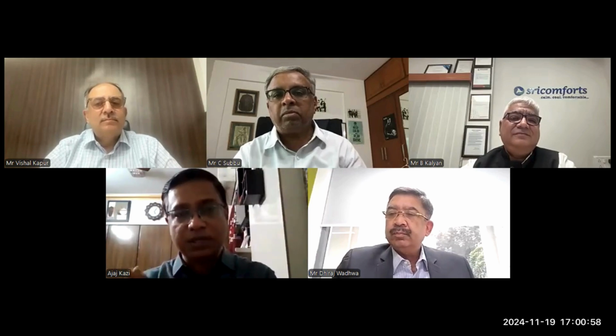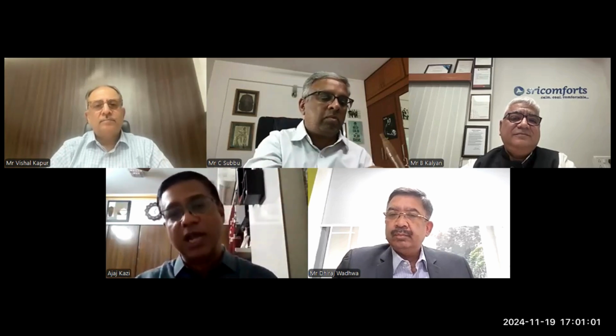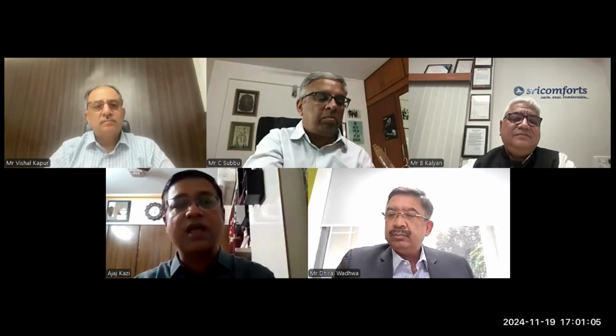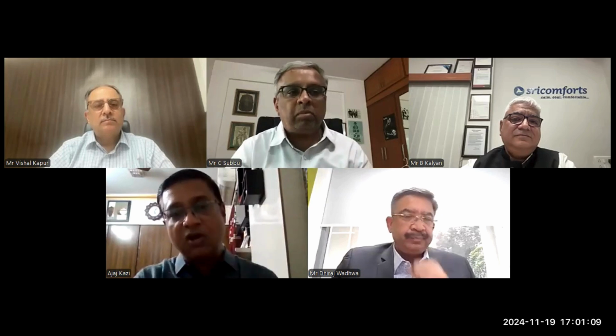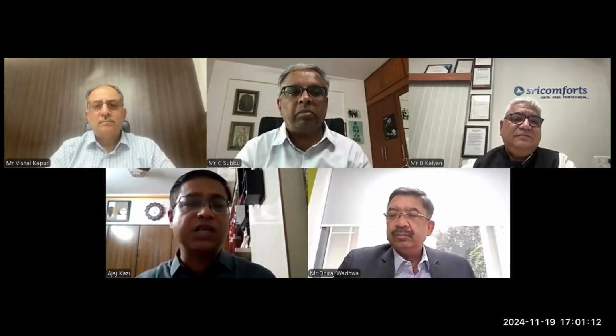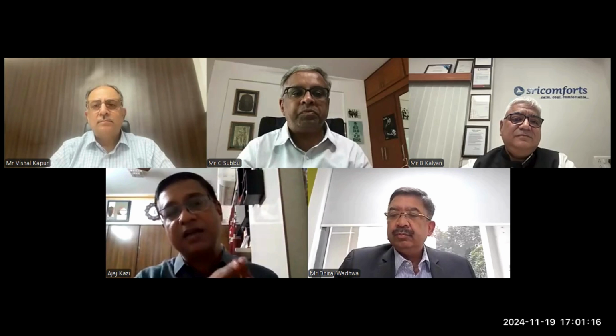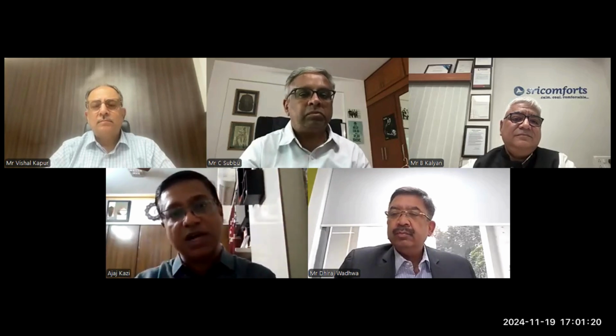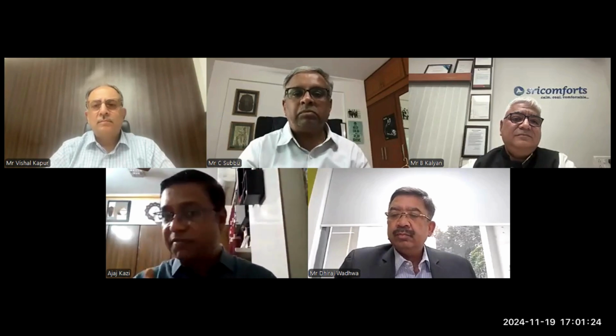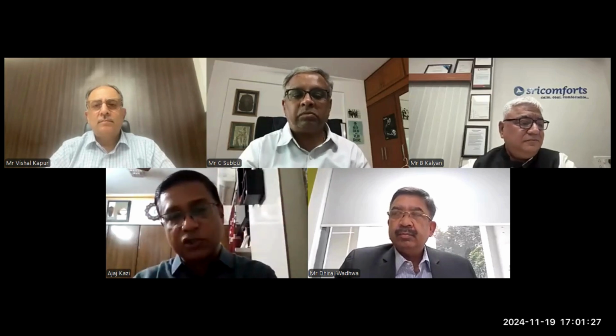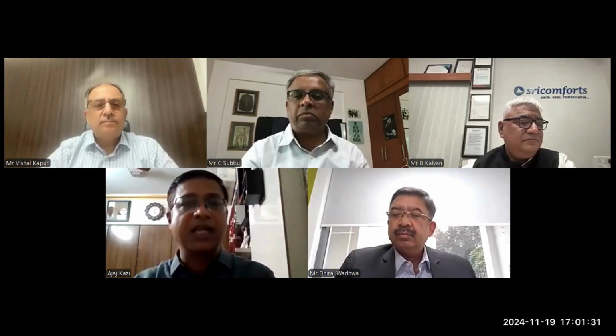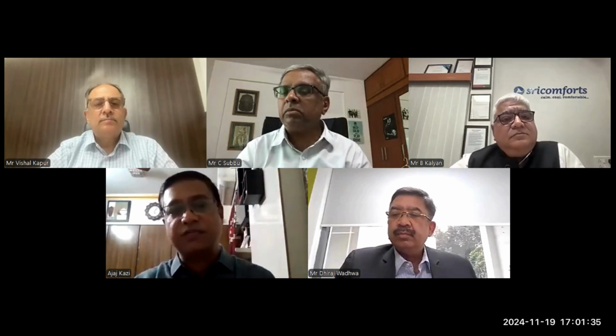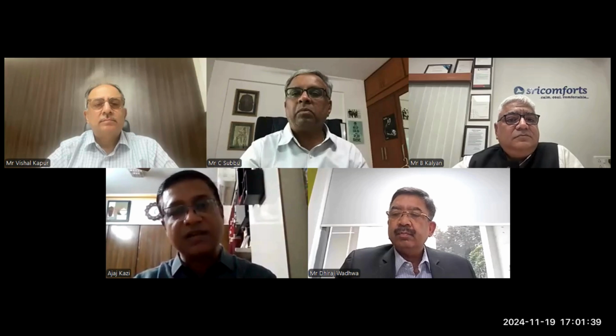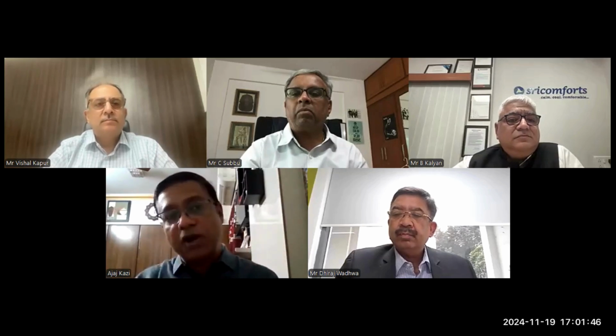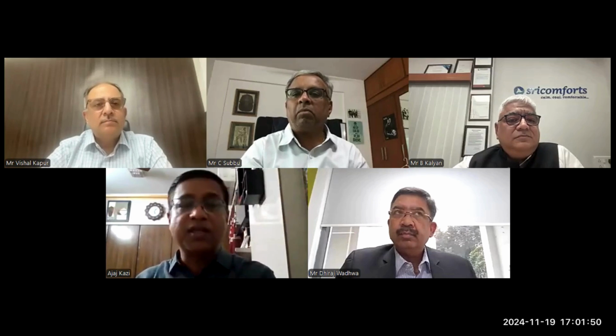When we have the basic data available, if someone suggests isolated retrofits or even total retrofits, I know through simulation what energy savings are possible with available technologies. If I go for that, I make sure the components being changed or retrofitted also get integrated into the BMS system. If that doesn't happen, my data doesn't come through. So once I've done isolated or total retrofits, I get data again from BMS, and only then can I compare the energy efficiency. Otherwise we're all just shooting missiles in different directions and getting nothing. I should have BMS in the system, get current energy consumption data, and if I go for retrofit, BMS should show me the difference in energy.